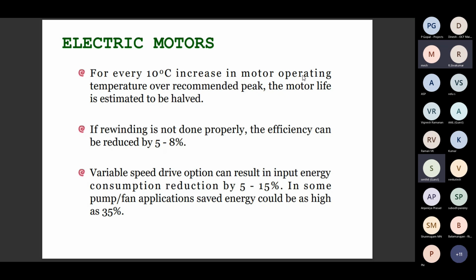Basically, in all industries, if any motor fails, it is given to a local workshop or an in-house team, mostly the local workshop. They dismantle the motor and rewind it. Once the motor is rewound, that means dismantled and assembled again by the local workshop, the efficiency will automatically reduce by 5 to 8%. Many foundries use motors that have been rewound more than 5 to 6 times. As per the BEE recommendations, a motor should be rewound only 2 or 3 times. After that, it can be scrapped and a new motor used. But in practice, it does not happen. Every time the motor is rewound, a minimum of 5% efficiency is lost. If it is rewound at least 5 times, a minimum of 20% efficiency will be lost, so we are using more energy. This is not noticed by the management.